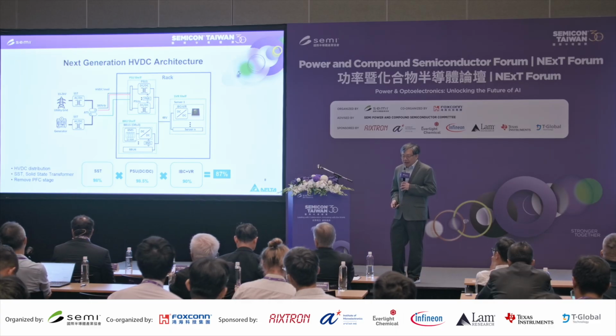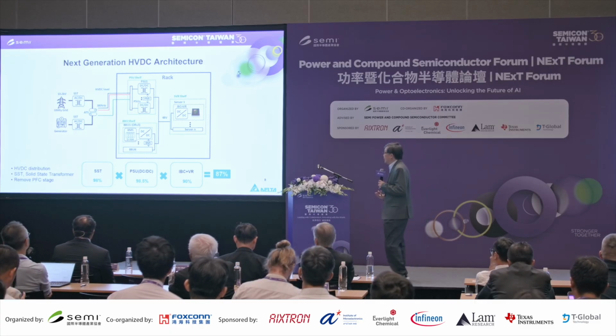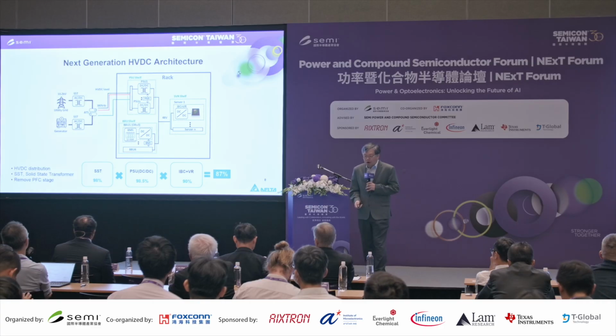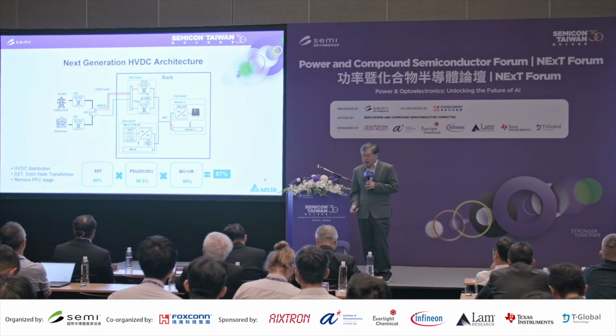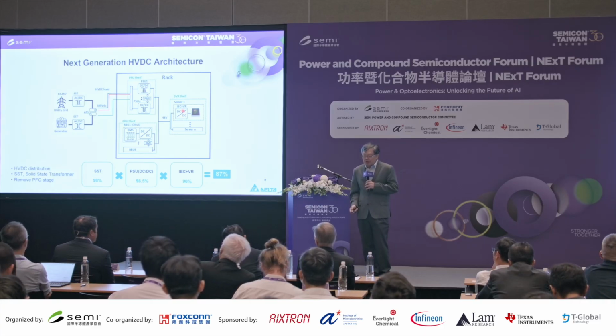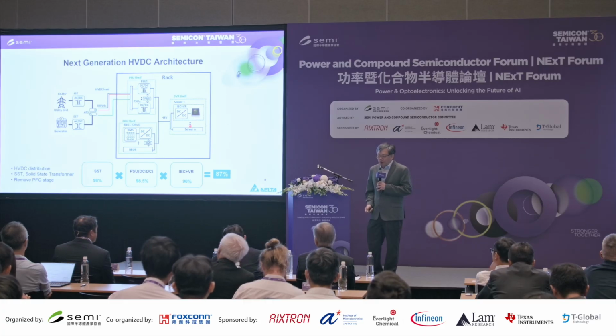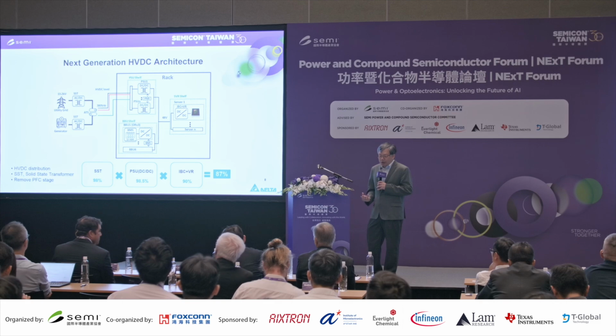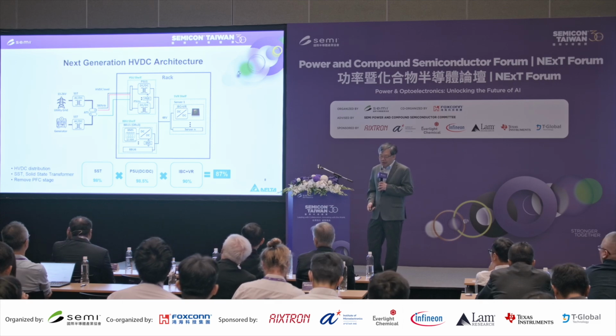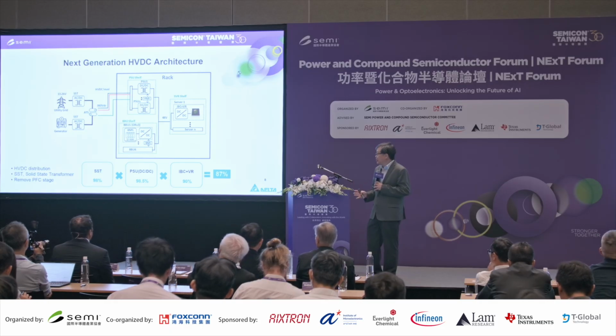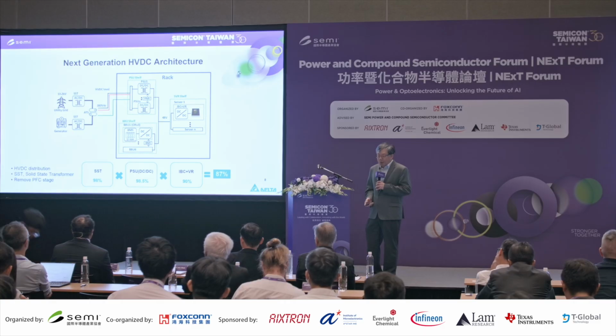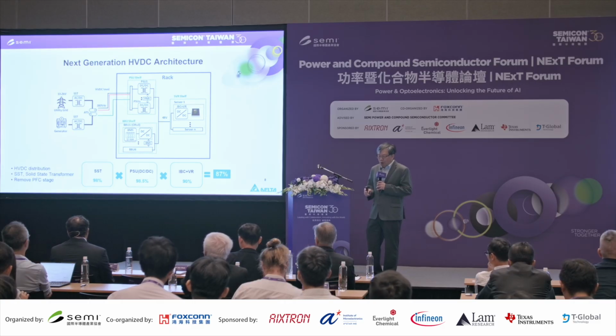Inside the DC rack, there are only DC-DC conversions. Everything goes from 400 volts to 48 volts, and all the way through the IBC plus the final voltage regulator down to like 0.75 volts to the chips. Because of the higher voltage, we can reduce the current, so the power efficiency can also be increased. So the architecture has changed from the current power rail to the rack.